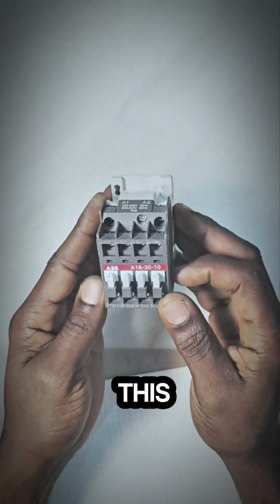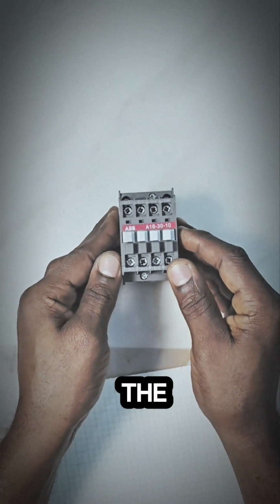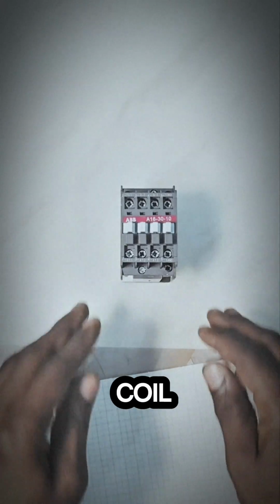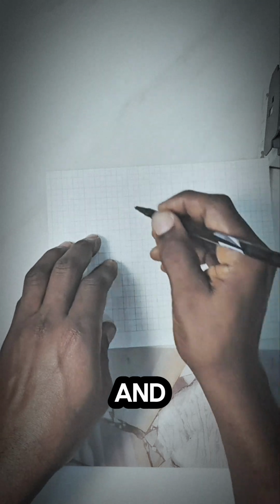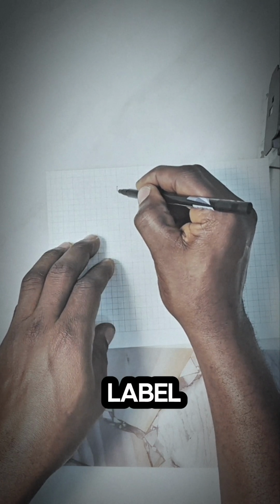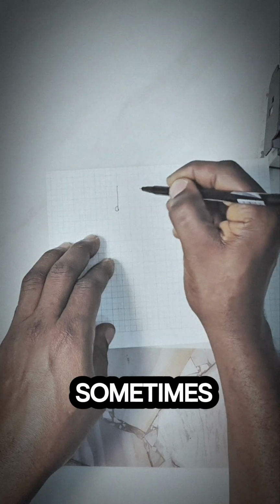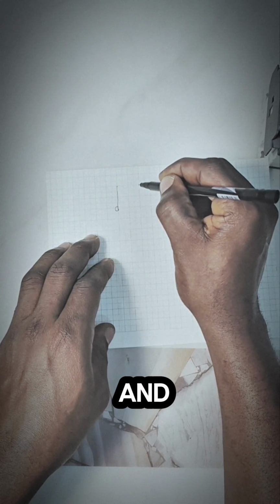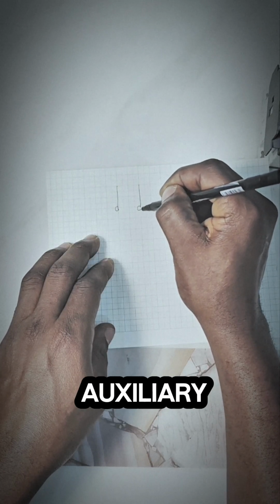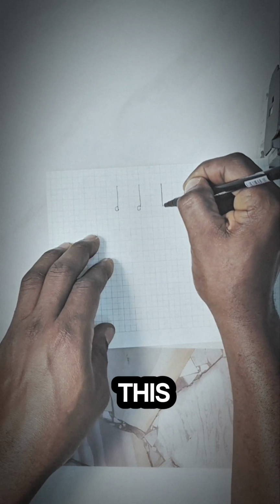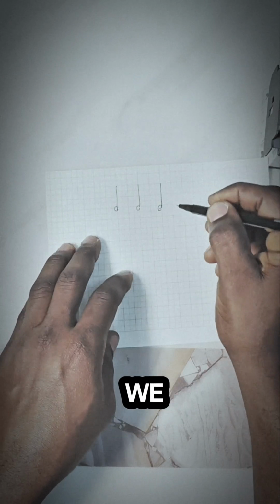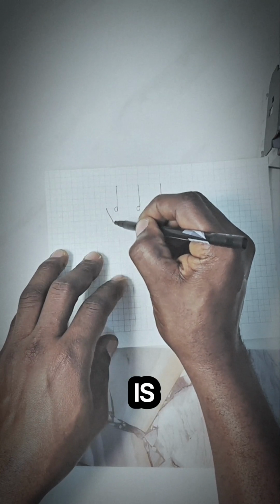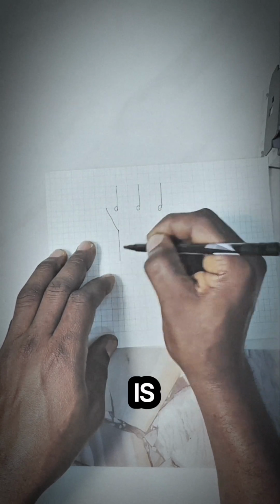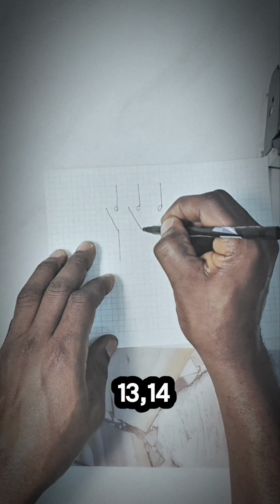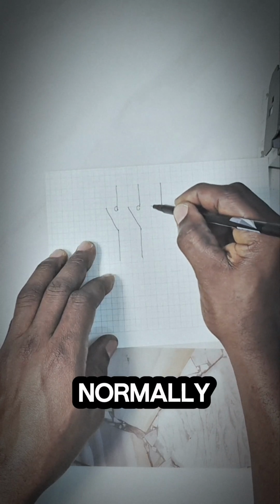This is operated by a magnet, which is the coil. This is the coil, and remember, the coil is labeled A1 and A2. And then, of course, you're going to have this dotted line, and then we label this 1, 2, 3, 4, 5, 6. Sometimes the auxiliary, you can have 13 and 14. This one is a normally open auxiliary contact, just the way we have on this one. So if we keep it side by side, 1,2 is 1,2, 3,4 is 3,4, 5,6 is 5,6, and then 13,14 is 13,14, and this is normally open.